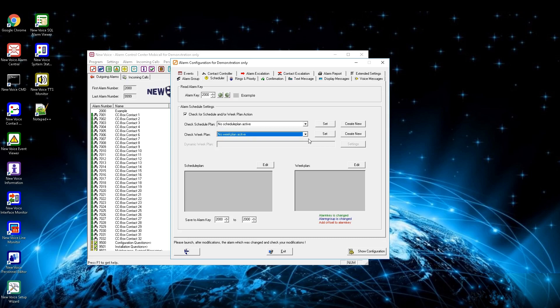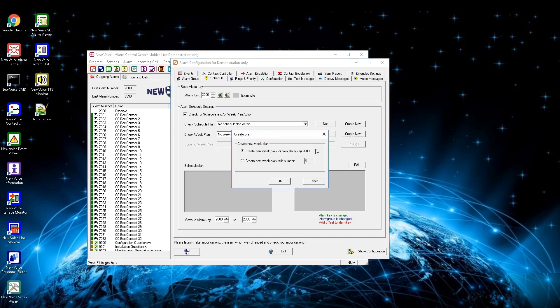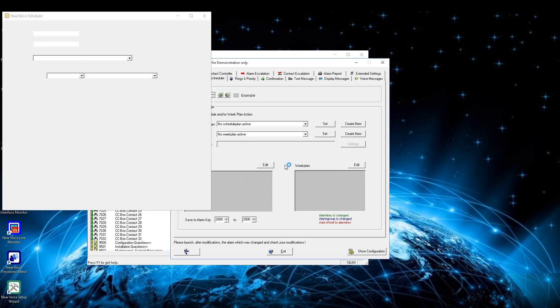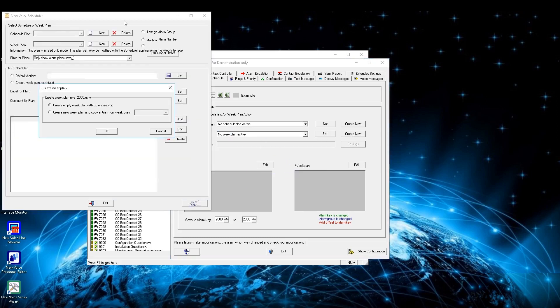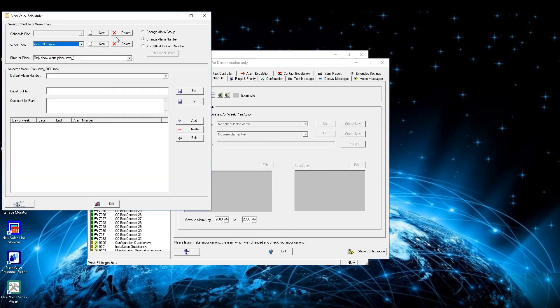Create a schedule or week plan by pressing the button create new beside the schedule plan or week plan drop-down menu. Choose if you want to use the alarm number as schedule plan number or give your own number. The next window is to create a new empty schedule plan or to copy from an existing one. In the new voice schedule that opened up you can define what should happen within or out of this time.